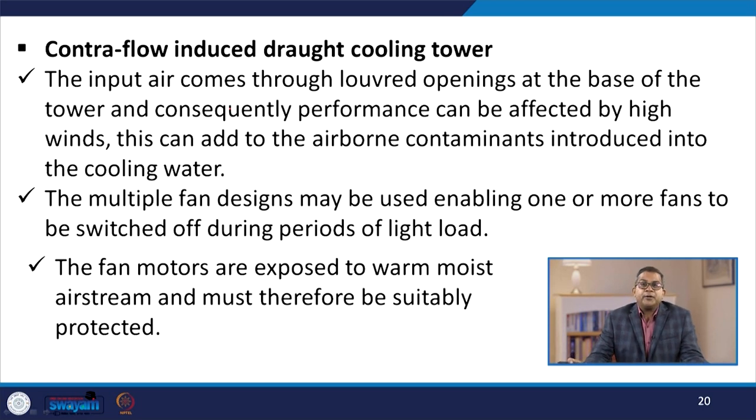Now, let us talk about the contra-flow induced draught cooling tower. The input air usually comes through louvered openings at the base of the tower, and consequently the performance can be affected by high winds. This can add to the introduction of airborne contaminants into the cooling water, and that sometimes is highly undesirable. Multiple fan designs may be used, enabling one or more fans to be switched off during periods of light load. In this way, you can enhance the energy efficiency.